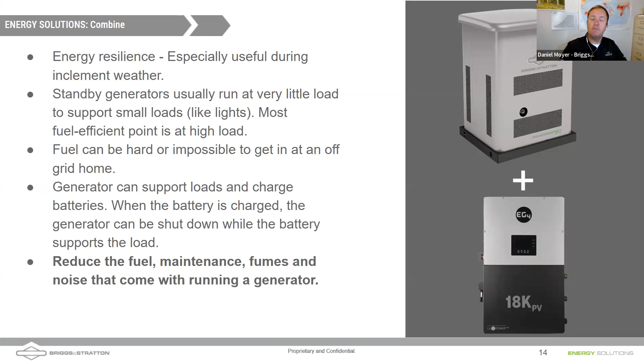So it's sometimes hard to get that fuel delivery. If you have to truck it in, what does that look like to drive into town, fill those up, and drive it back? Usually when you have a generator on a system, it's not running at its most fuel efficient point—it's running at just a couple thousand watts to keep lights on. The reason we install a larger generator than you'd normally be using is for startup motor loads, like an air conditioner.